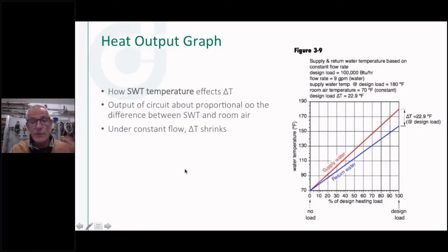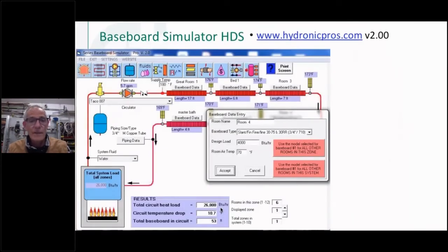As you can see down here, as it gets warmer outside or whatever causes the load to change, warmer in the building, you're doing some cooking, whatever, it'd be nice to modulate that burner down and always match that load instead of shutting off, shutting on, shutting off, shutting on. And if we do that with temperature instead of flow rate, I can get a nice stable parallel curve, I guess you would call it, by modulating that temperature. And I'll show you in this example here.